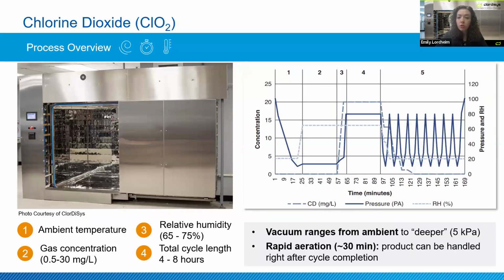And then just to give another little overview before we send it off to Jeremy, chlorine dioxide is an ambient temperature process. We can have a gas concentration that can fluctuate depending on your needs for your process. The relative humidity is typical for other gas sterilants, 65 to 75% relative humidity, and a cycle time is relatively short, meaning 4 to 8 hours on average. We can have vacuum levels that can fluctuate depending on your needs, and we have a very rapid aeration process. So as I mentioned, we're going to go off to Jeremy to dive deeper into compatibility of packaging with chlorine dioxide.